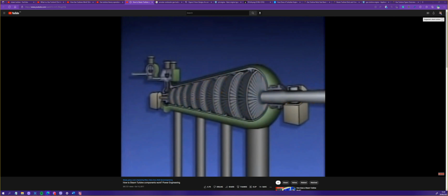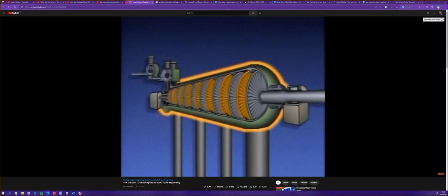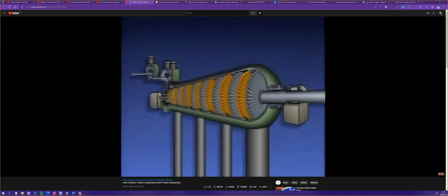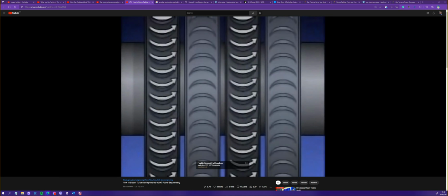Mounted to the turbine casing are diaphragms. They are positioned in the casing between the wheels. The casing and diaphragms are stationary parts of the turbine. Diaphragms are similar to wheels in that they are round hubs and they have blades. The diaphragm blades are sometimes referred to as nozzles. The distinction between diaphragms and wheels is the way they function during turbine operation. Diaphragms are stationary, and their blades are fixed in position. Their function is to direct the flow of steam leaving one set of rotating blades into the next set of rotating blades. Wheels, on the other hand, are moving parts.